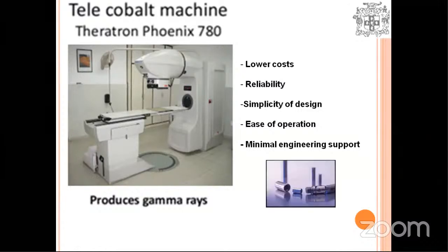This is a pretty simple machine with a radioactive cobalt source in the head of the machine, which is basically giving out radiation 24/7. The patient lies down on the couch, and based on our dose calculations, the time is calculated, the source comes to the head of the machine, and radiation is delivered to the patient. So what we are using here are gamma rays for the treatment of patients.